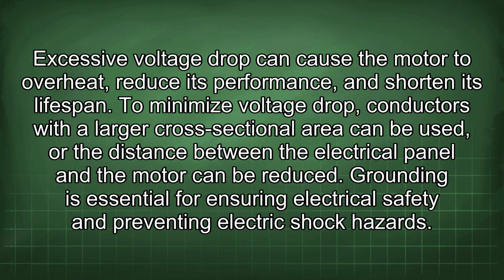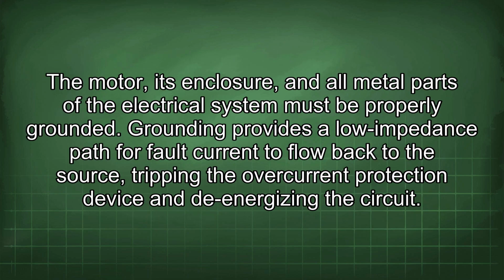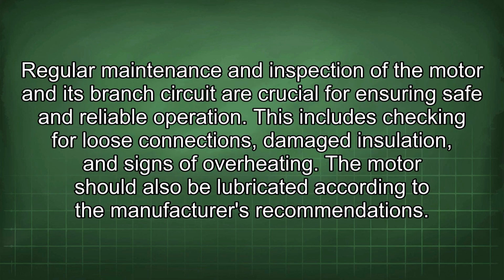Grounding is essential for ensuring electrical safety and preventing electric shock hazards. The motor, its enclosure, and all metal parts of the electrical system must be properly grounded. Grounding provides a low impedance path for fault current to flow back to the source, tripping the overcurrent protection device and de-energizing the circuit. Regular maintenance and inspection of the motor and its branch circuit are crucial for ensuring safe and reliable operation. This includes checking for loose connections, damaged insulation, and signs of overheating. The motor should also be lubricated according to the manufacturer's recommendations.